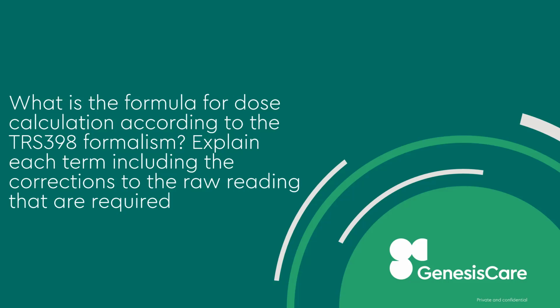For the dose calculation according to TRS 398, we need the meter reading from the electrometer. Then we multiply with the N_D,w calibration factor, which we get from the calibration certificate provided by the company, and we need the beam quality correction factor, k_Q.